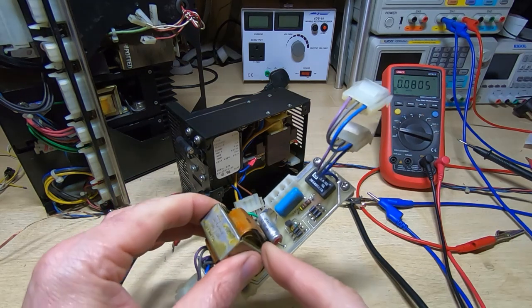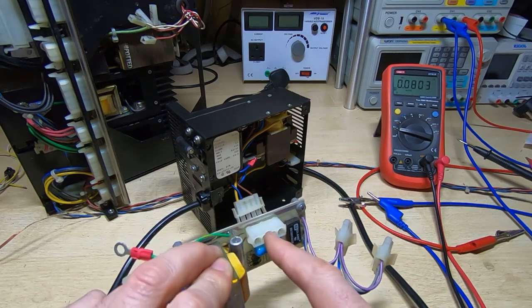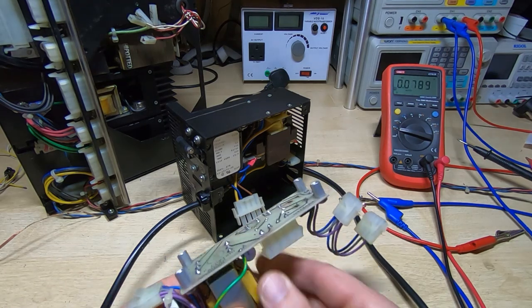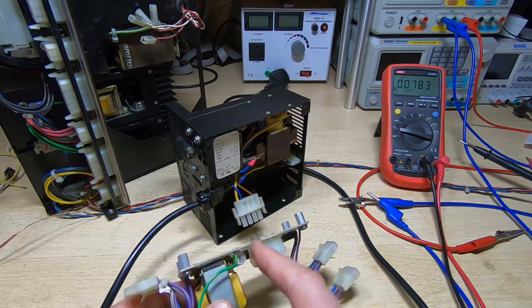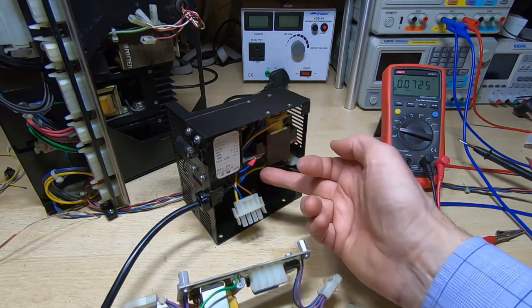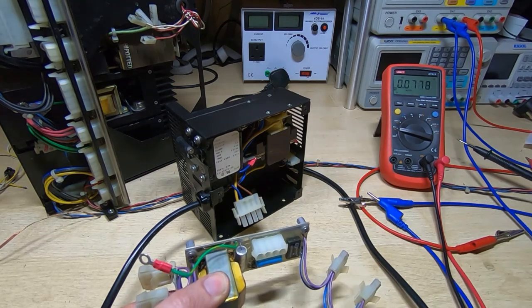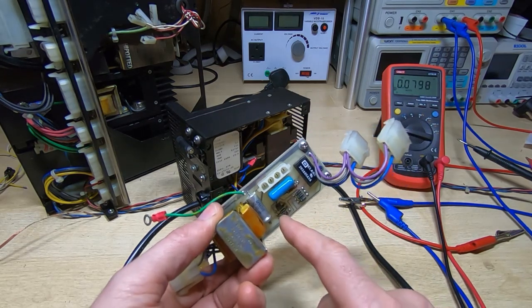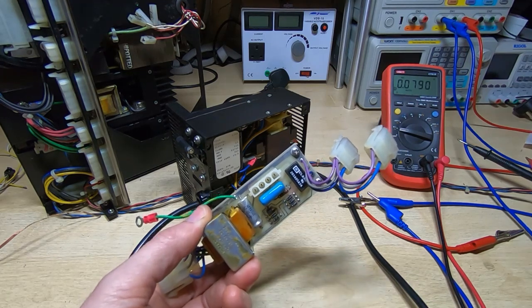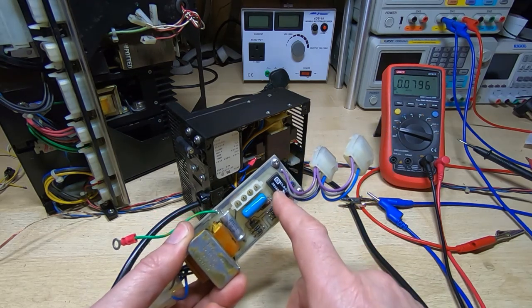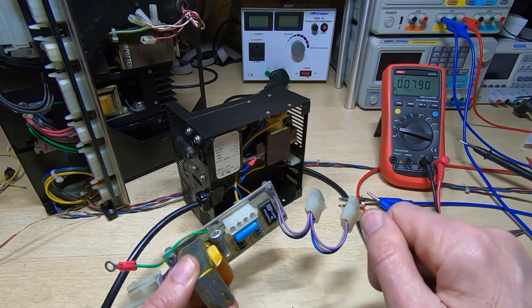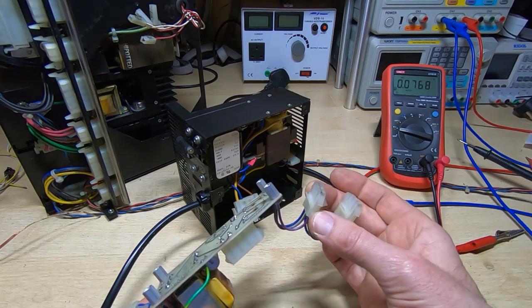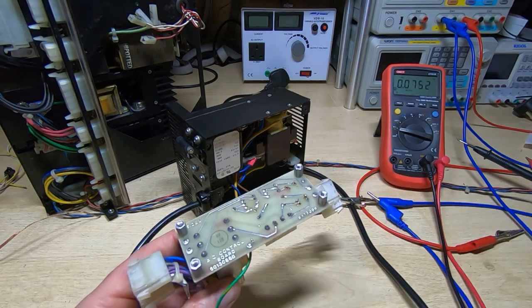And so I started looking into the power control board. That's where the fault really has to be. Which is this board sits inside the power input module. And it's a very simple circuit. So all that's really in here is a bridge rectifier formed with these diodes. It's fed from mains input. So there's only three connections really in terms of power. You've got mains live and neutral coming in. And then one of the pins going out goes to the contactor solenoid. And the other end of that contactor solenoid goes directly to the live wire coming in on the output of the main switch. So it's very simple. The mains coming in goes through a transformer. And that's using a full bridge rectifier creates a DC voltage, about 30 volts. And that is used to drive an opto isolated triac. And that's turned on and off either through the power switch on the front of the machine, or using one of the remote control sockets on the back of the machine. These are all wired in parallel, so they're exactly the same. It doesn't matter which one you operate.